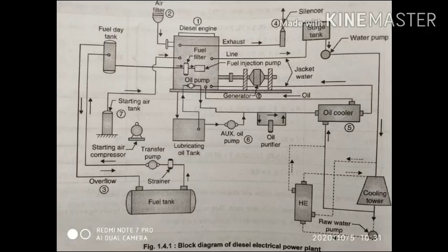Pistons and cylinders require special lubricating oil. The forced feed lubrication is mostly employed. In this system of lubrication, the lubricating oil is drawn from the sump by means of a pump and is passed through the strainer and then through a filter in order to remove the impurities. Usually the lubricating oil is hot when drawn from the sump. If it is not, it should be heated first before passing through the filter in order to decrease its viscosity and make the filtration easy. The lubrication oil cost of diesel power plants is about 30% of the fuel cost.